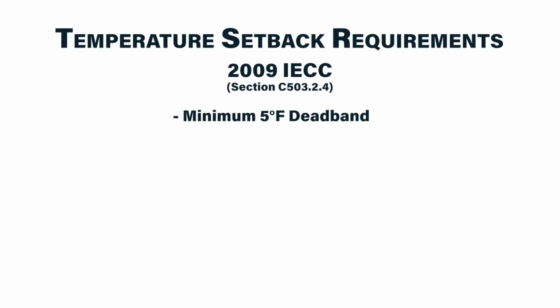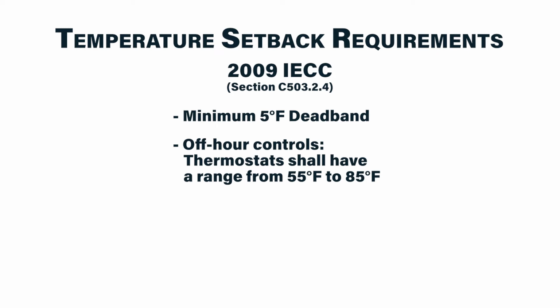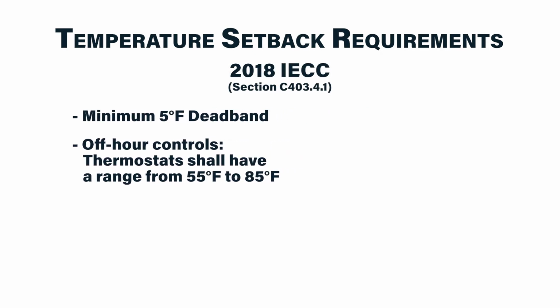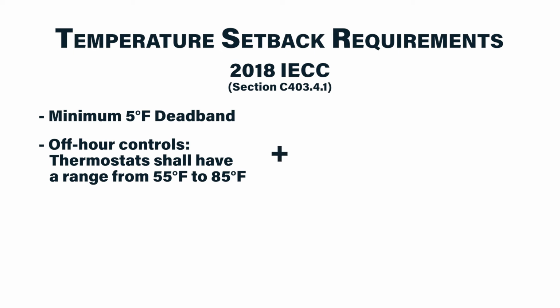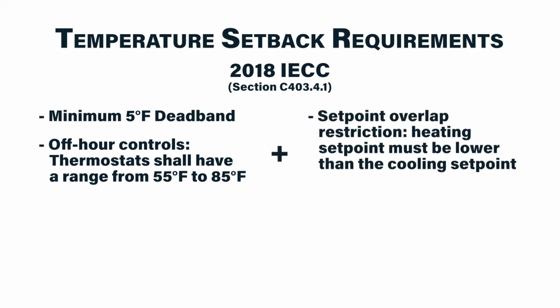The 2009 IECC also required thermostats to have a wide range to allow for off-hour setbacks to save energy when the building is unoccupied. The 2018 IECC adds a few more definitions to some of these items. The first is that you can't overlap heating and cooling set points. If you have a zone with separate heating and cooling set points, you can't set your heating set point higher than your cooling set point.